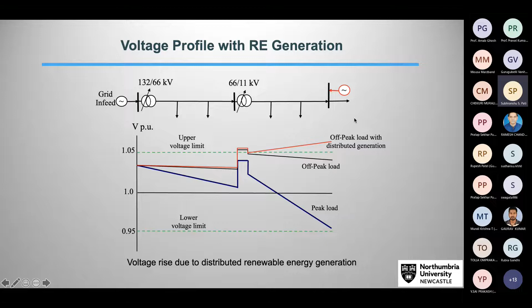whether it is off-peak or peak demand. Once you put distributed generator, there is potential here that the voltage at the far end, or even voltage here, this 11 kV feeder might increase above the limit because you now have supply here, some of the demand. You have reduced the voltage drop in the feeder and therefore increase the voltage.